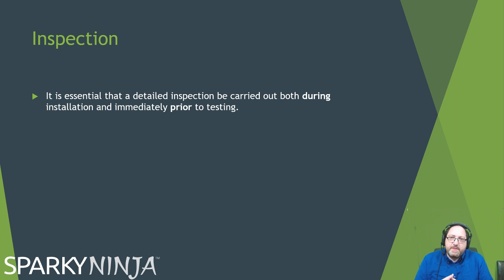With regards to the inspection, it is essential that detailed inspection be carried out both during installation and immediately prior to testing. It's obviously incorrect to have a practice where one team does an install, then another team comes afterwards to do a test. The initial verification has to be carried out during the installation procedure, because there'll be inspections for different erection methods.